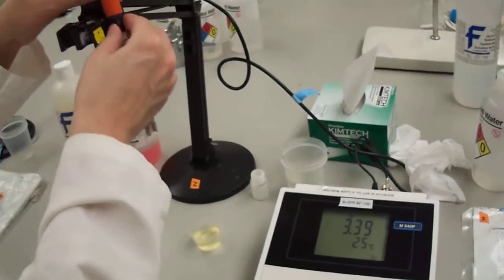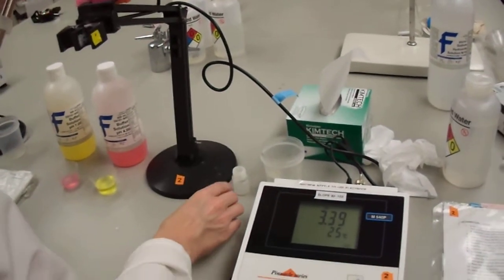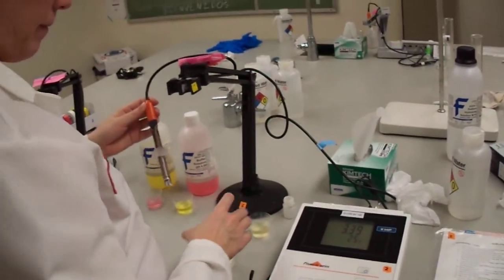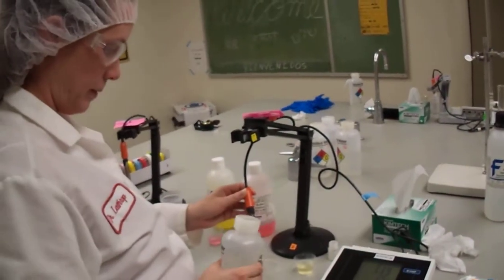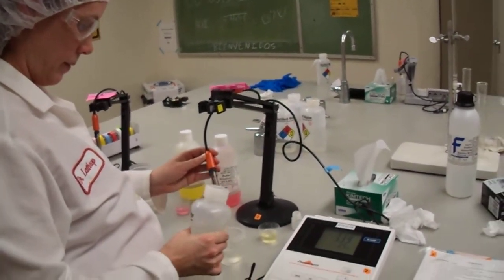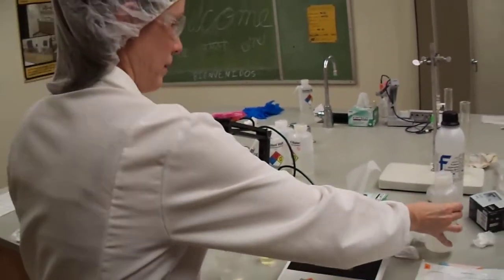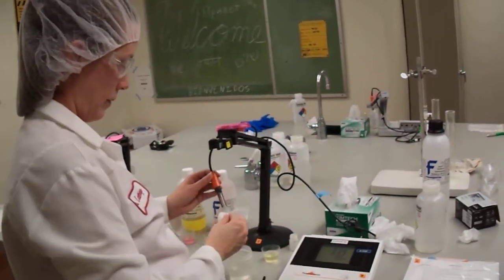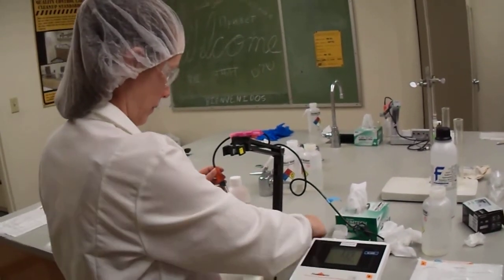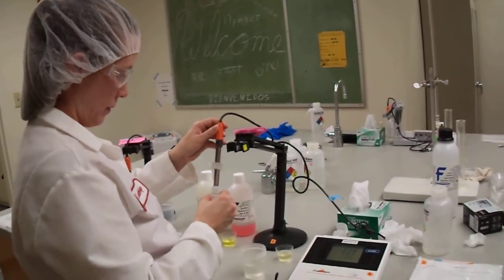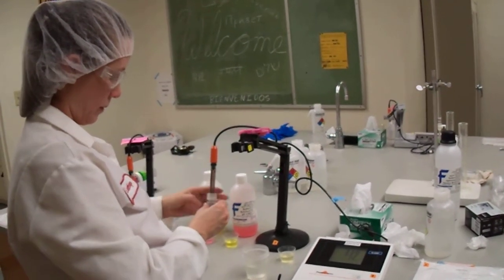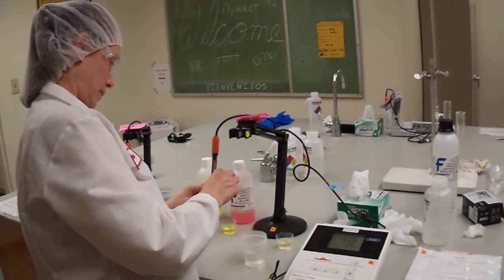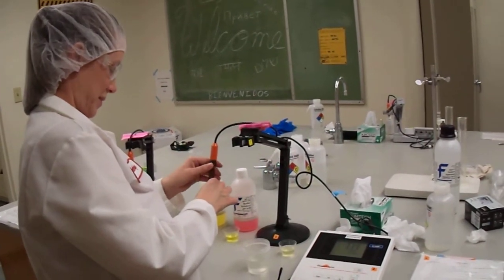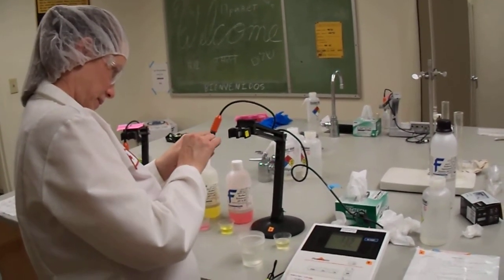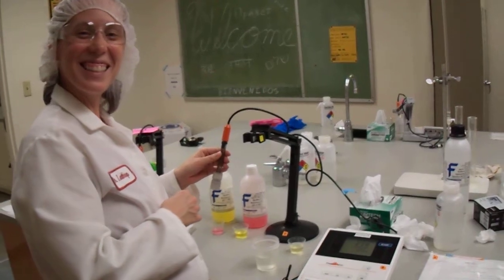Upon conclusion of testing, you must rinse the electrode with DI water and place it in the storage reservoir, and be sure to close the tab at the top of the electrode. We're done.